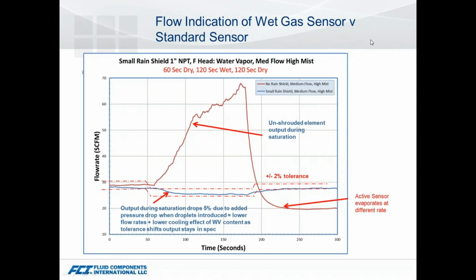One last item on the wet gas sensor is comparing it to an unshrouded sensor. So just a quick show here as we introduce moisture in a little test stand. The red line is typically what you would see from a standard constant power driven flow meter. As we introduce more moisture, the cooling effect of that moisture versus the gas is causing us to get this false high spiking reading. And depending upon the content, it can be quite large.